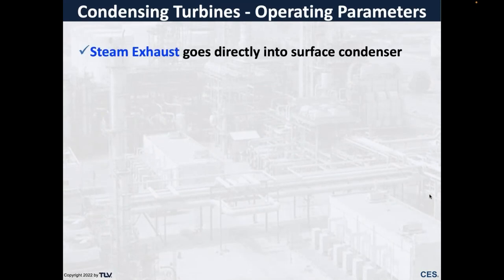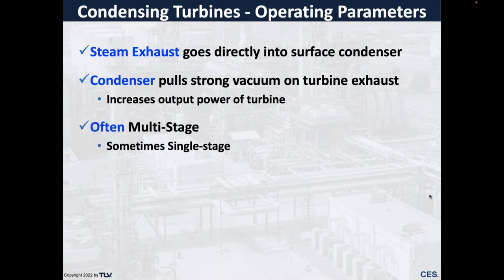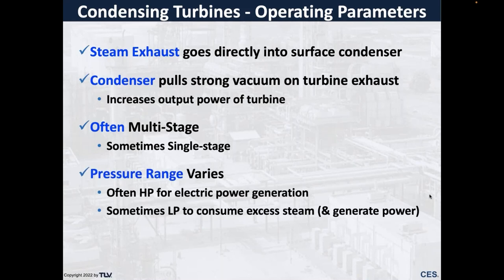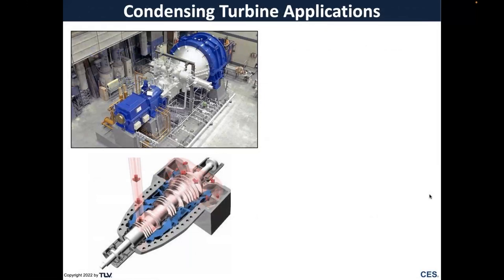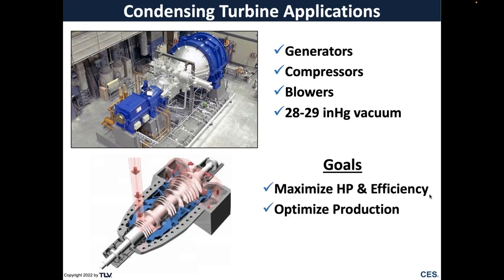For condensing turbines, the exhaust goes directly into a surface condenser. The condenser pulls a strong vacuum when working properly. These are often multi-stage and the pressure range varies. A condensing turbine application is rather sophisticated — used for things like wet gas compressors and main air blowers, which can pull 28 to 29 inches of vacuum. The goals are to maximize horsepower and efficiency and to optimize production.